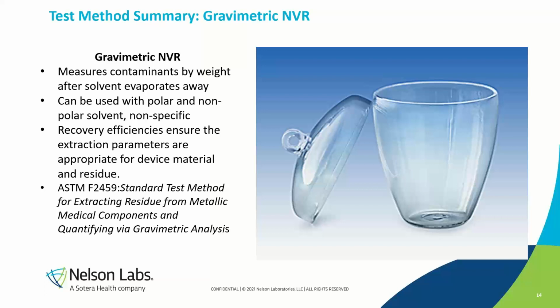ISO 19227 lists this ASTM F2459 standard, as well as ISO 10993-12, which is kind of the regular biocompatibility extraction part, as extraction options for cleaning validations. So we like to use the 30-minute sonication because we want to be as aggressive as possible at removing that surface residue without degrading the device. We're not directly concerned with the clinical relevance because we're also talking about just the efficacy of the cleaning steps. So we want to be aggressive in the extraction. A 30-minute sonication in an appropriate solvent is pretty aggressive. But it's all going to come down to a recovery efficiency. I should back up and continue the remainder of the analysis here.